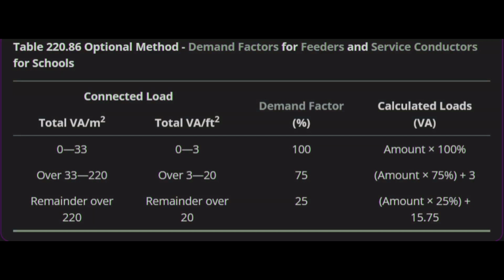So to sum up the main point, Section 220.86 is a really powerful tool. It's performance-based, you could say. It lets designers swap out a standard, often oversized calculation for one that uses demand factors, specifically reflecting how a large school actually operates. Its efficiency is literally engineered into the code. Yeah, it really acknowledges the reality of usage. The gym lights are on, but maybe the library wing is quiet, or the kitchen is busy, but classrooms are empty. That diversity.